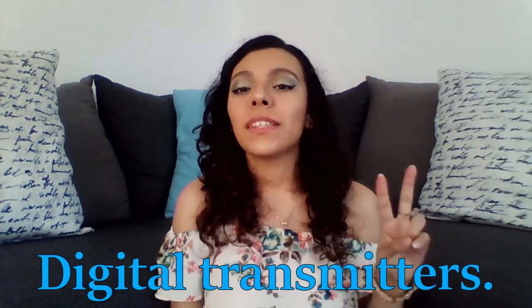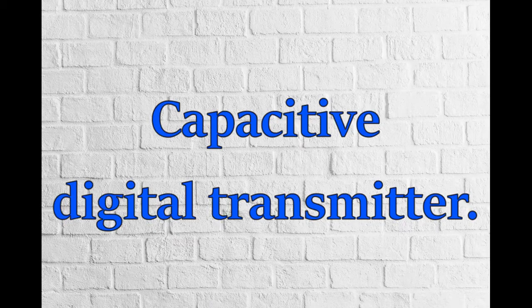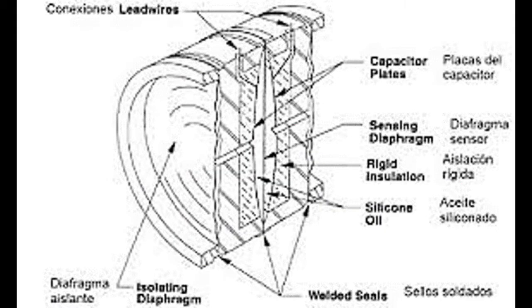There are two basic models of intelligent digital transmitters. The first is the capacitive model, which is based on the variation in capacitance produced in a condenser that has two fixed plates joined by an internal diaphragm that move when pressure is applied to external diaphragms. The pressure transmission occurs through oil, which fills the condenser.